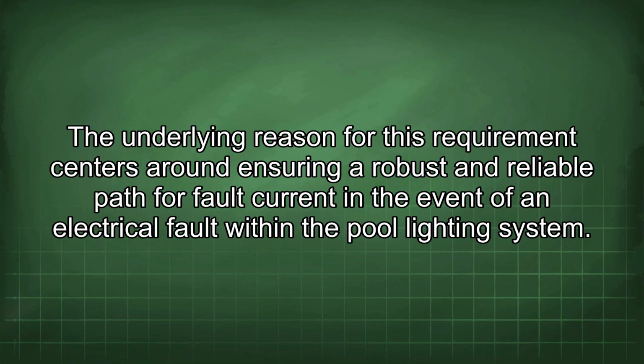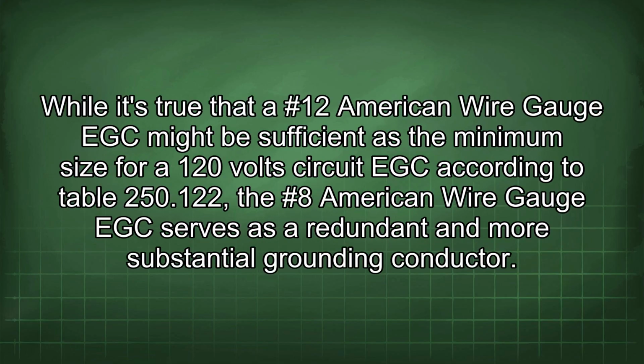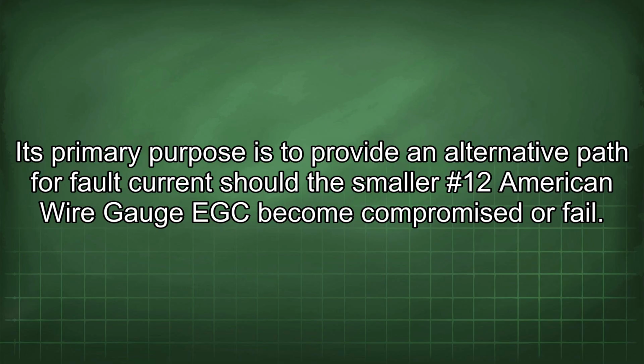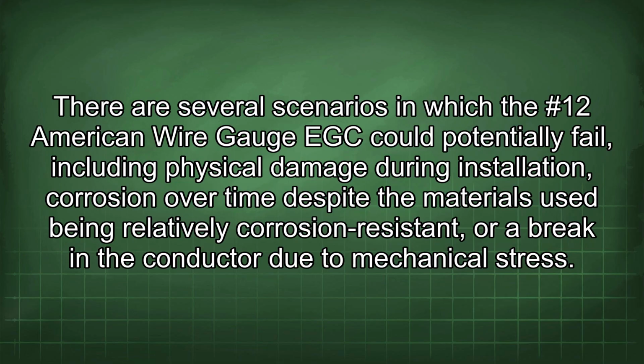The underlying reason for this requirement centers on ensuring a robust and reliable path for fault current in the event of an electrical fault within the pool lighting system. While a #12 American wire gauge EGC might be sufficient as the minimum size for a 120-volt circuit EGC according to Table 250.122, the #8 American wire gauge EGC serves as a redundant and more substantial grounding conductor. Its primary purpose is to provide an alternative path for fault current should the smaller #12 EGC become compromised or fail. There are several scenarios in which the #12 EGC could potentially fail, including physical damage during installation, corrosion over time despite the materials used being relatively corrosion resistant, or a break in the conductor due to mechanical stress.